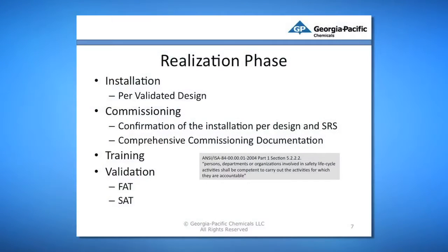The next phase is the realization phase. The installation is done, of course, based on the validated design, but the SIS commissioning includes confirmation that equipment and wiring are properly installed, the energy sources are operational, all instruments are properly calibrated, field devices are operational, the logic solver itself and all the I/O related to that are operational, and all parameters of the configuration are validated.